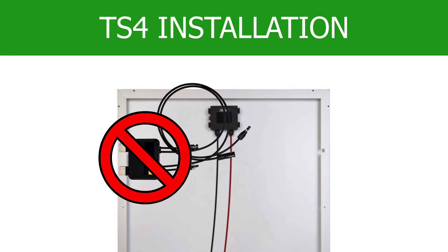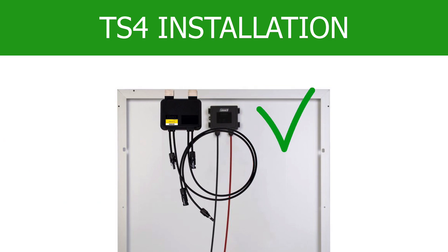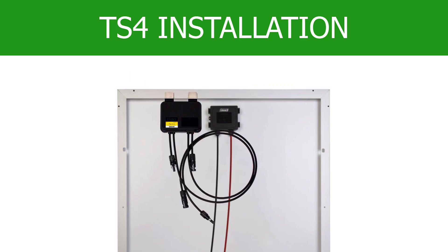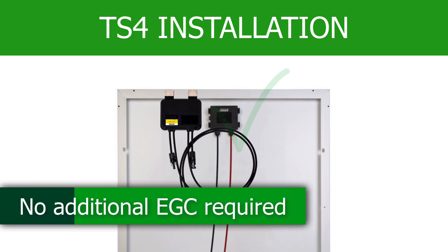Mounting the TS-4 in any other position than described in the installation manual is a violation of the warranty. Ensure the TS-4 is properly secured to the module. The clips bite down on the module frame and create a bond to ground. Consequently, TIGO units do not require separate grounding.